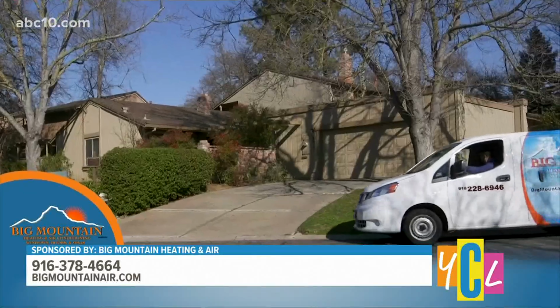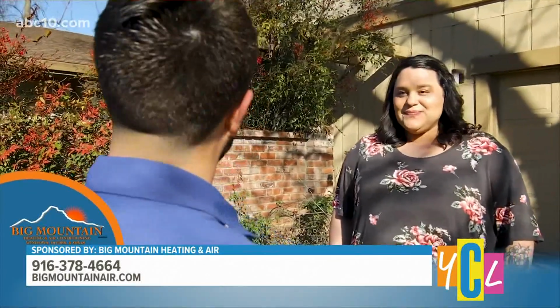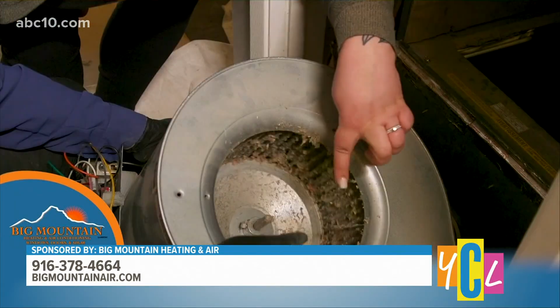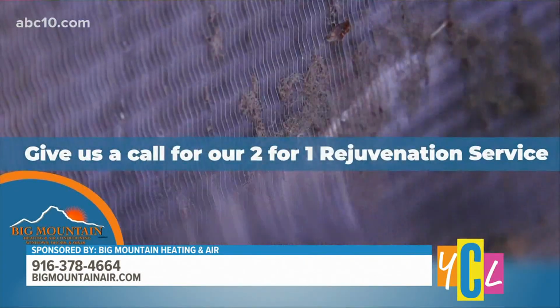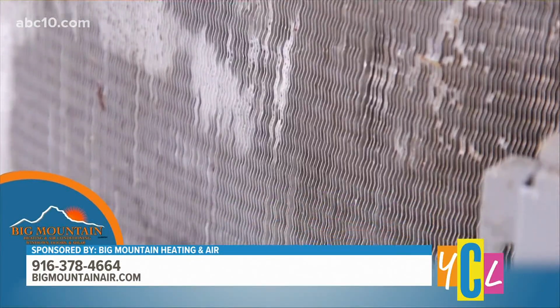I think people don't realize the biggest reason for a breakdown is dirt. It's the main reason. And it starts there at the filter, like you can see. It gets into that blower motor. You have no idea. Really, it's hidden. And like that right there, you wouldn't see that because it's normally covered.